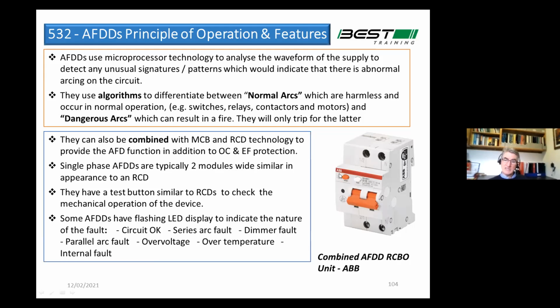Basically, they have a clever piece of electronics in here that monitors the waveform. When you have abnormal or dangerous arcs on the installation due to loose connections or breakdown in insulation, it causes little spikes, like a signature, I think is the term they use. It sets up a signature pattern, if you like, on the sine wave, and these devices are specifically tuned to identify that. It can differentiate between normal arcs, because we have normal arcs every day of the week. Every time you turn on a light, or the washing machine goes from spin program to drum program, you get arcing across contacts, and they're normal arcs. Or motors, the vacuum cleaner has a series motor with brushes. All those little arcs are normal, and the device ignores those, but will trip out on a dangerous arc as such.